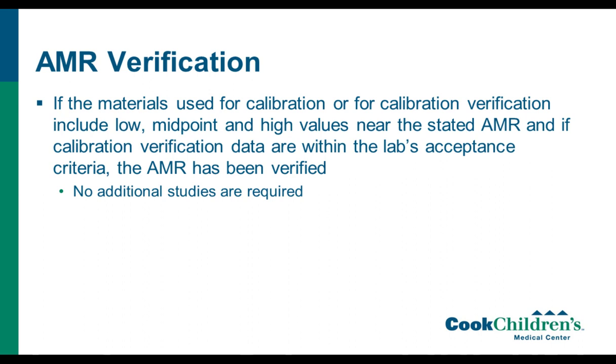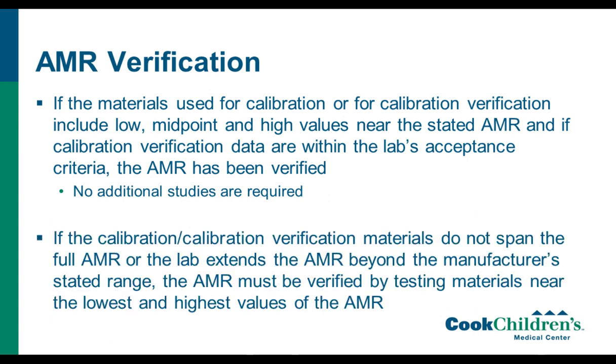AMR verification may actually not be required depending on how you're running your specific test. So if when you run your calibration verification, you're using low, midpoint, and high values near the stated AMR, so near the high and low, and if your calibration verification meets your acceptance criteria, then you actually don't have to perform a second verification. You don't have to do a specific AMR verification. That's already been met by your successful calibration verification.